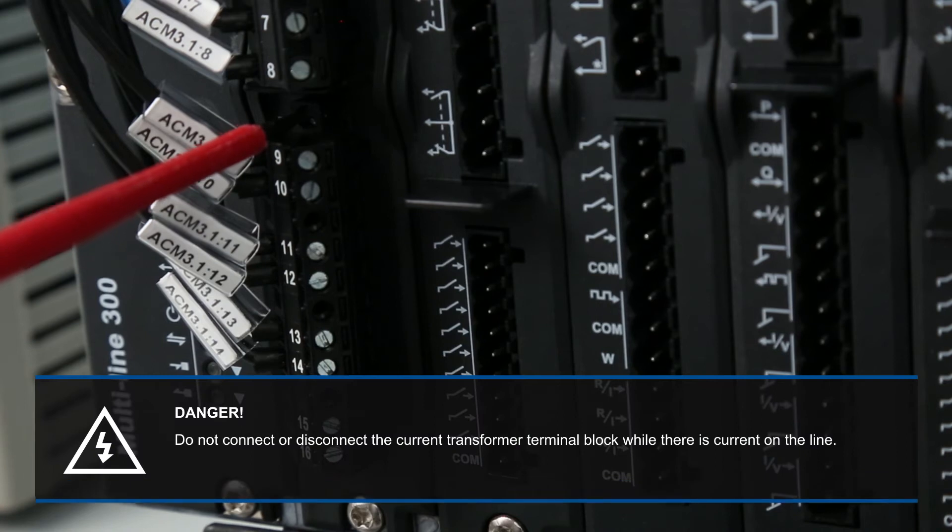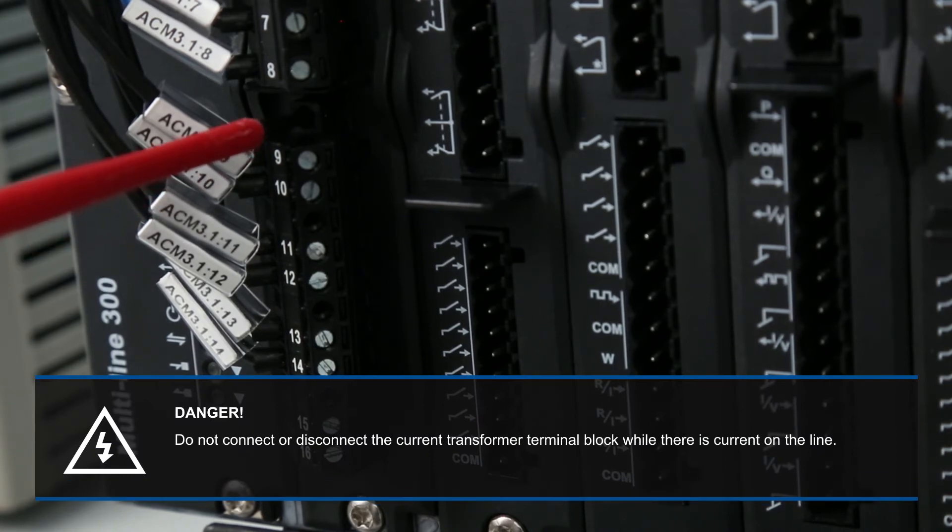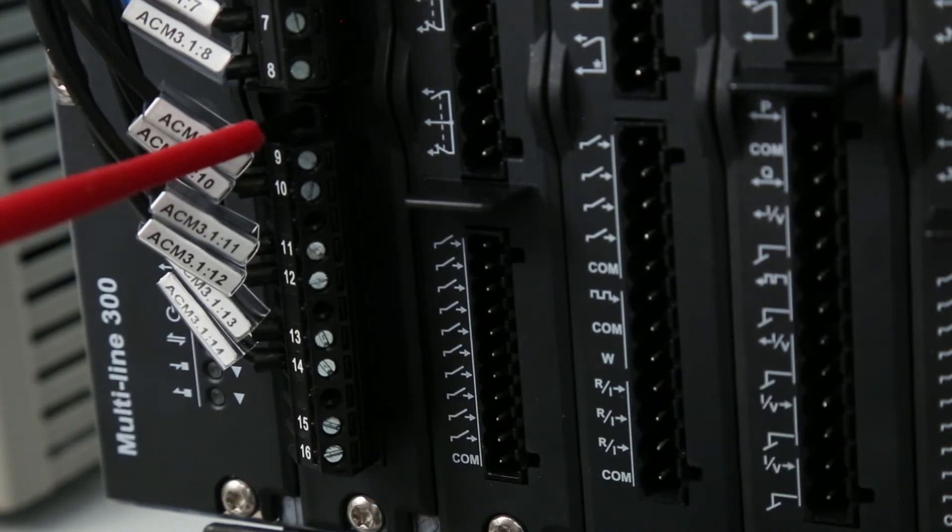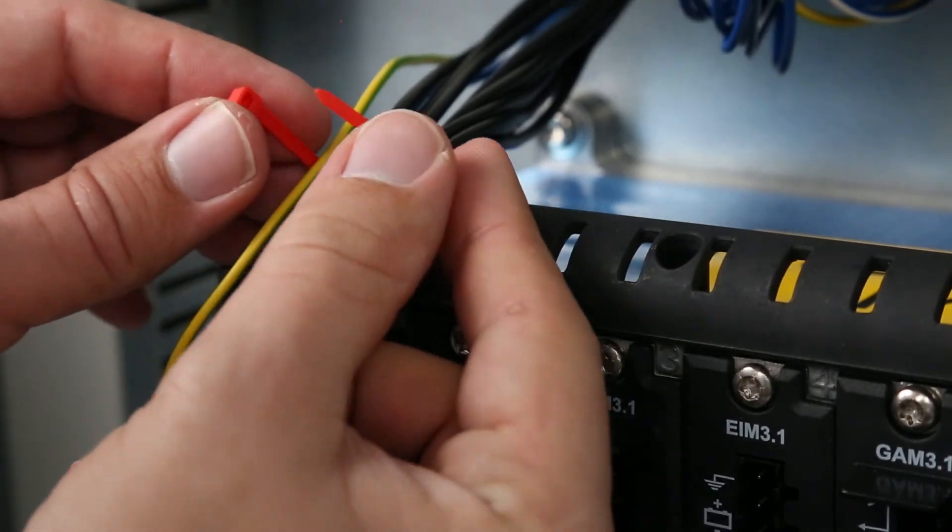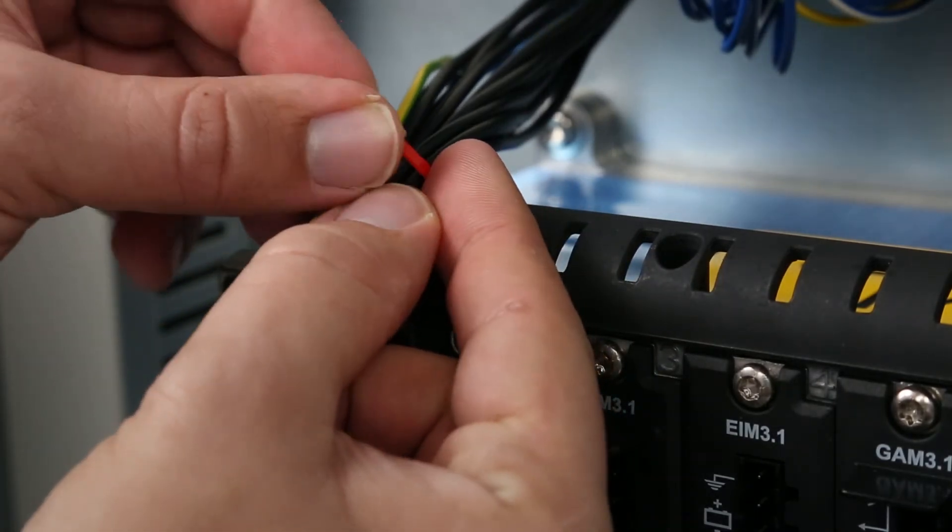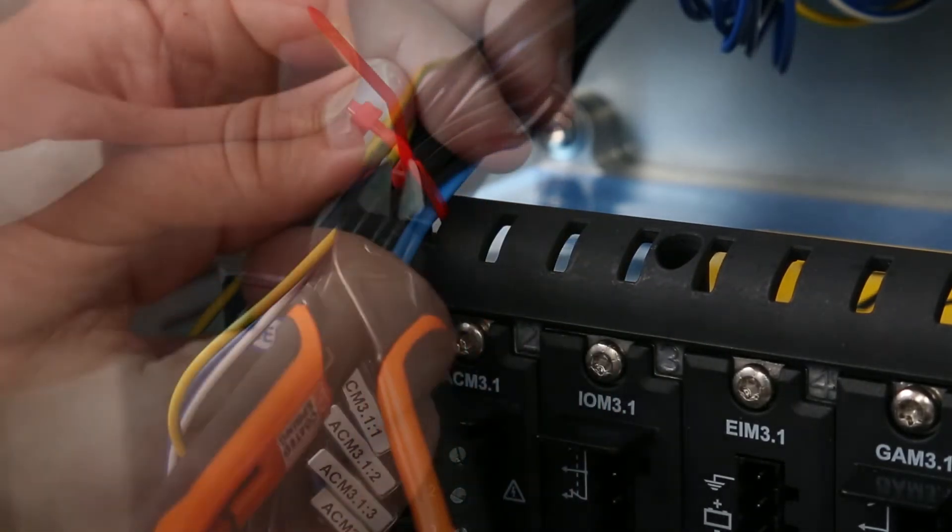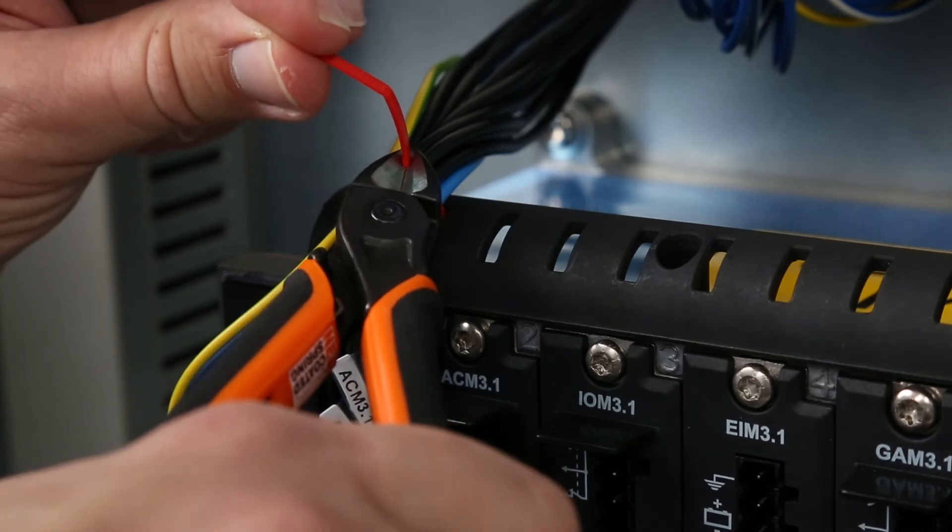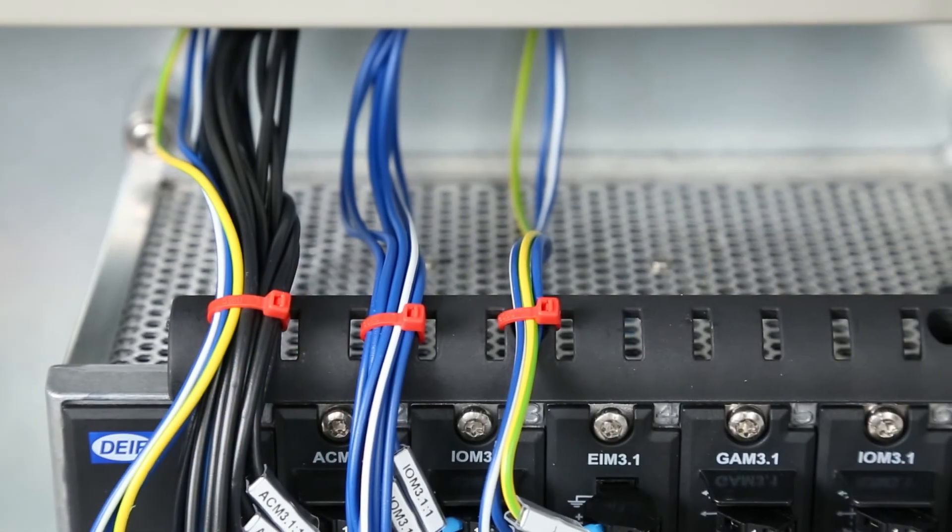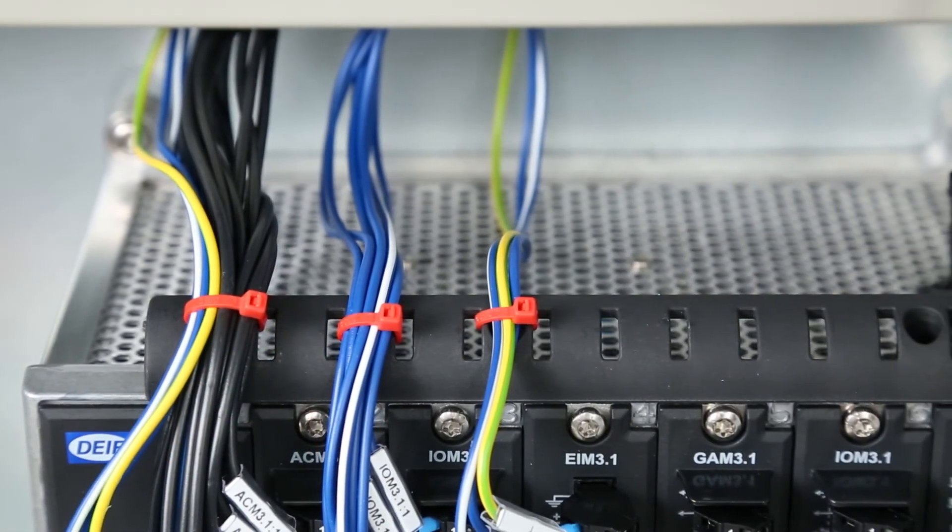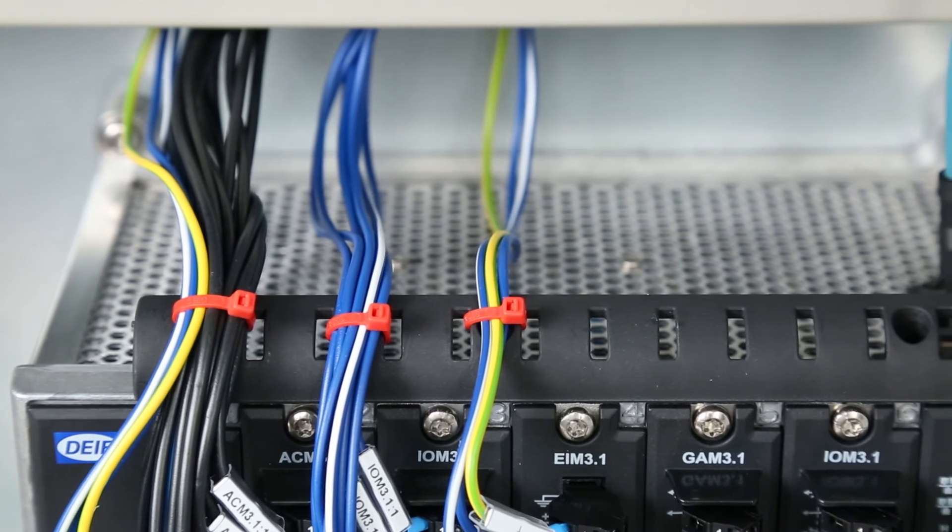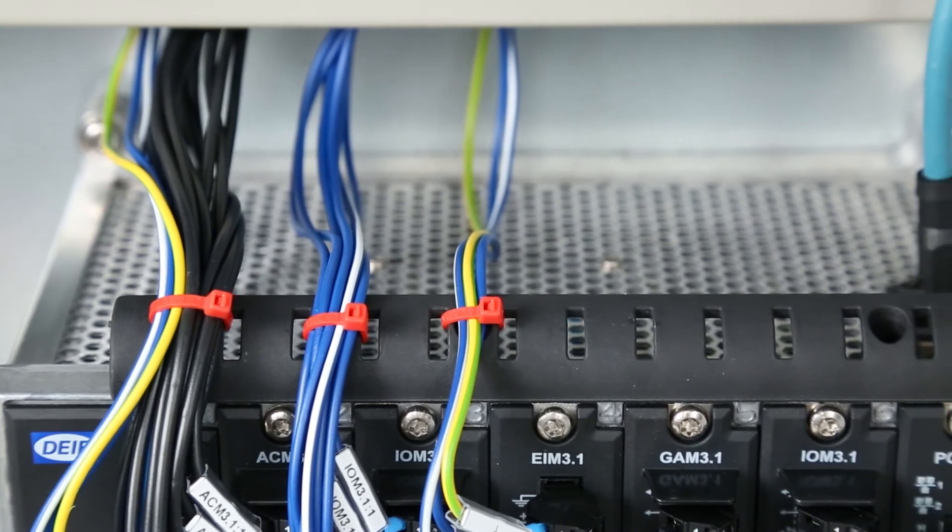Ensure the current measurement terminal block is screwed into the module. You can use cable ties to hold the cables in place. The cables and cable ties must not block more than 20% of the ventilation holes.